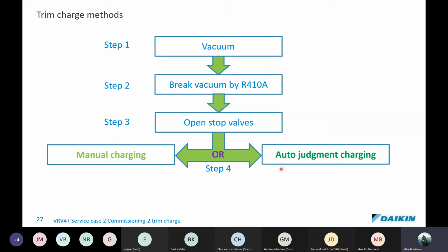So remember, we said that you would pull the vacuum on the system. That vacuum would have been pulled down to below 500 microns. We would have then done a vacuum decay test, and if it passed that, it was a 100 micron climb in less than an hour, no more than that. And if it's a lot less, then well done. Then we break the vacuum with some R410A. We'll break it with the required amount that's calculated from the formula that we've just been working with, and we'll charge it into the liquid line, and then we will open the valves.